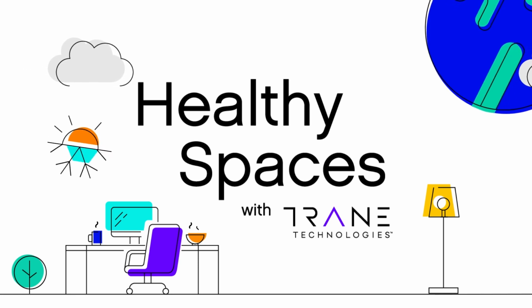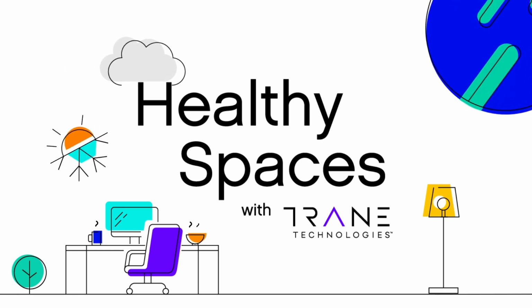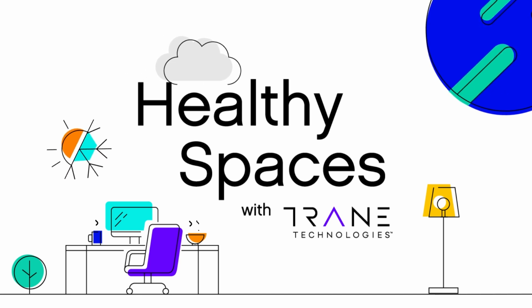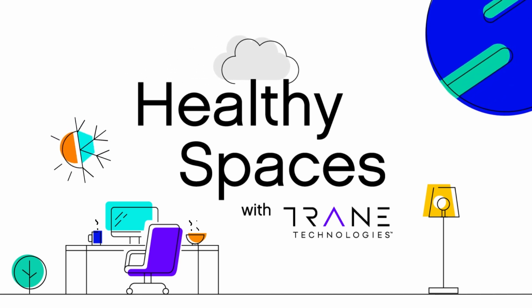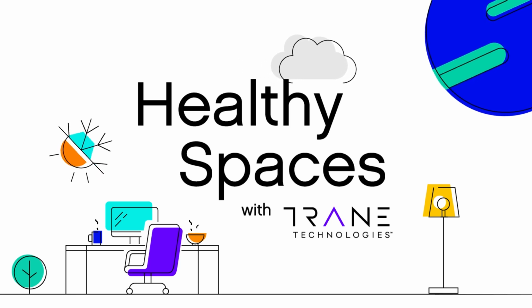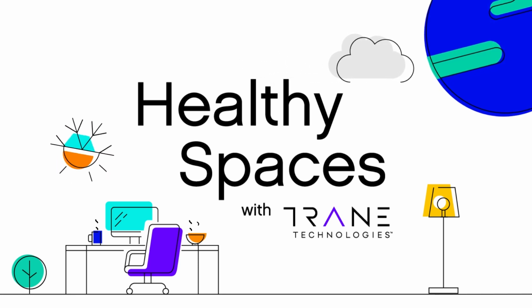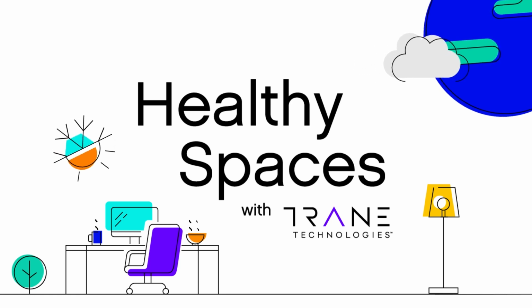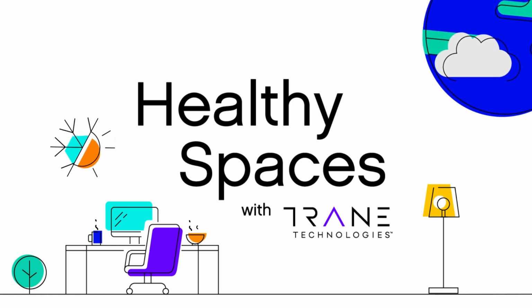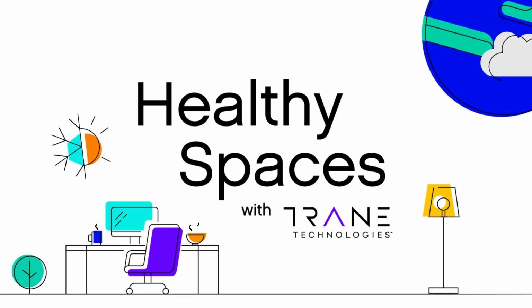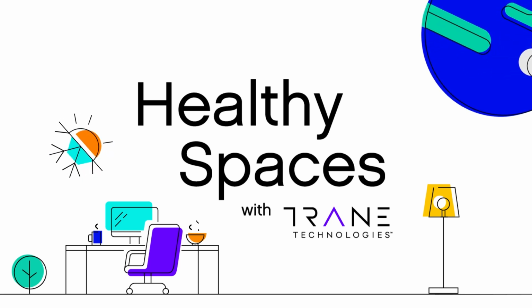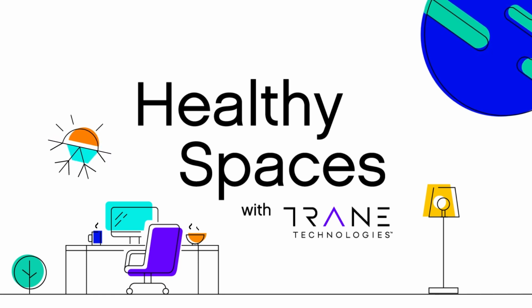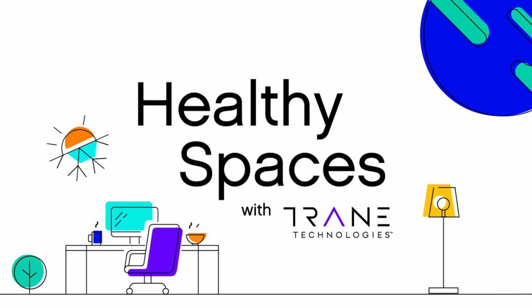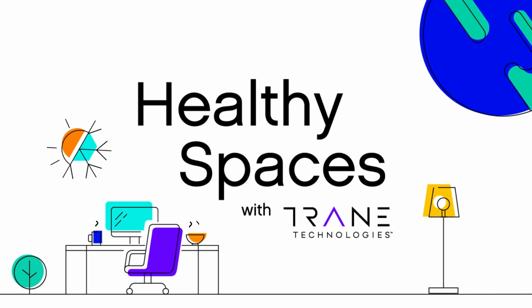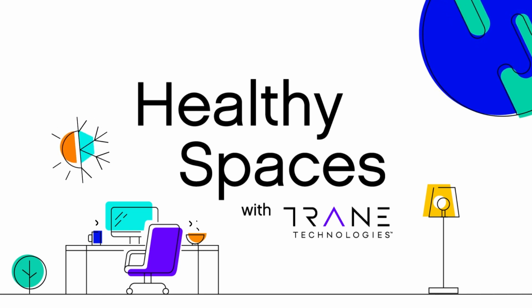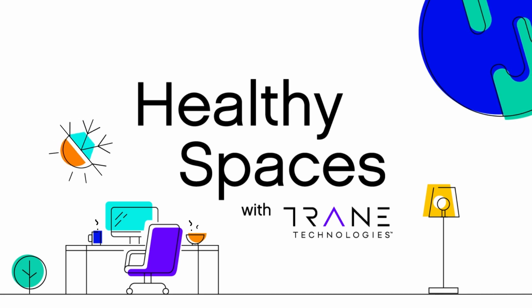I said, well, first of all, if you think about Trane Technologies and the HVAC industry, it represents about 15% of all greenhouse gas for heating and cooling of buildings. And what we've been able to do at Trane Technologies was really disrupt the conventional way of thinking for heating and cooling. In the past, you used to have a heating plant, we'll call that a boiler, and a cooling plant, we'll call that a chiller, and they operated as independent systems. What our clever scientists and engineers have been able to do is, because we like to think of things at the system level, we said let's create a system around this and not have them work independently.